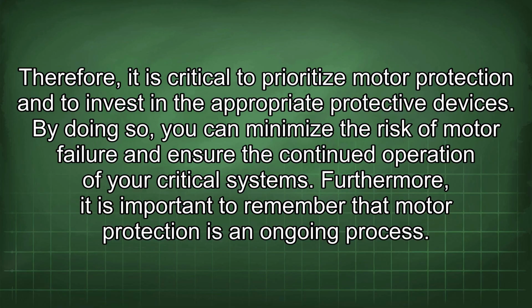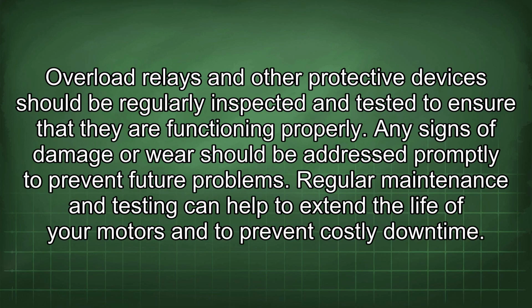By doing so, you can minimize the risk of motor failure and ensure the continued operation of your critical systems. Furthermore, it is important to remember that motor protection is an ongoing process. Overload relays and other protective devices should be regularly inspected and tested to ensure that they are functioning properly. Any signs of damage or wear should be addressed promptly to prevent future problems. Regular maintenance and testing can help to extend the life of your motors and to prevent costly downtime.